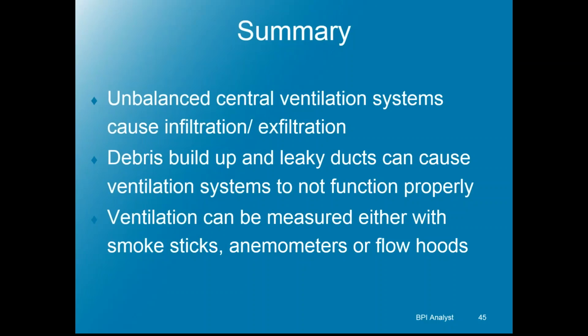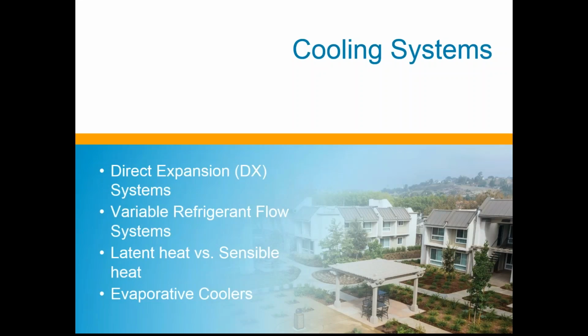So in summary, with unbalanced systems, the problem is you don't know where the makeup air is coming from. Debris buildup in ventilation systems is going to hamper their operation, of course. And then you want to measure and just verify. Even just using a piece of toilet paper against the fan will tell you qualitatively if it's blowing the right direction and kind of how well it's working, qualitatively only. And we'll take a break there.